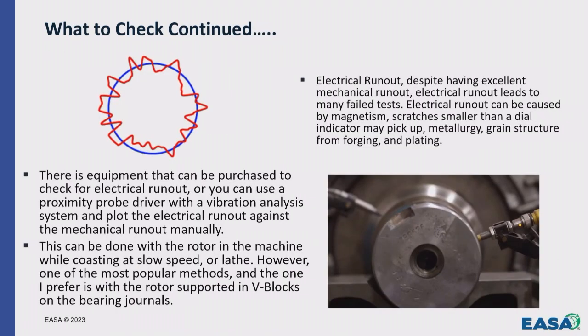Then we mentioned electrical runout a little bit. The first thing that affects it is Gauss or magnetism. We're essentially measuring the electrical field around the shaft. And electrical runout, you can have terrible electrical runout even if the shaft surface is perfect. And that was what got me on the front end in the first job that we really failed. So picture the blue circle at the top left. That's your mechanical surface, almost perfect. And then the red would be where we measured the electrical runout and compared the two against each other. And so you can see they're not even close in resemblance.